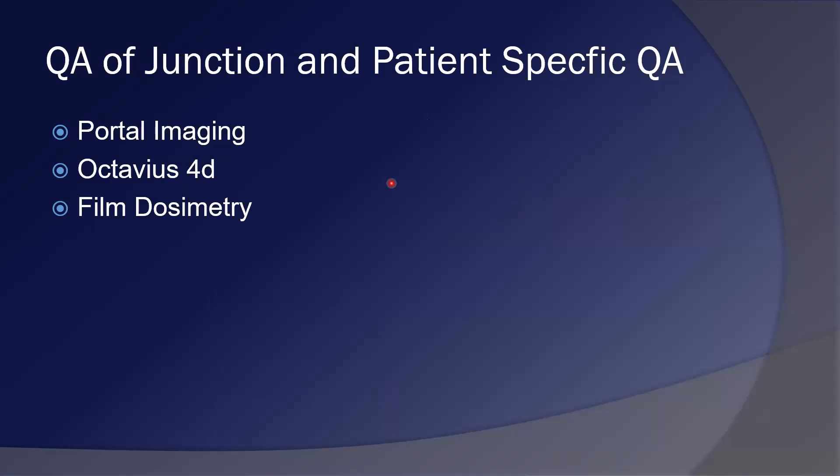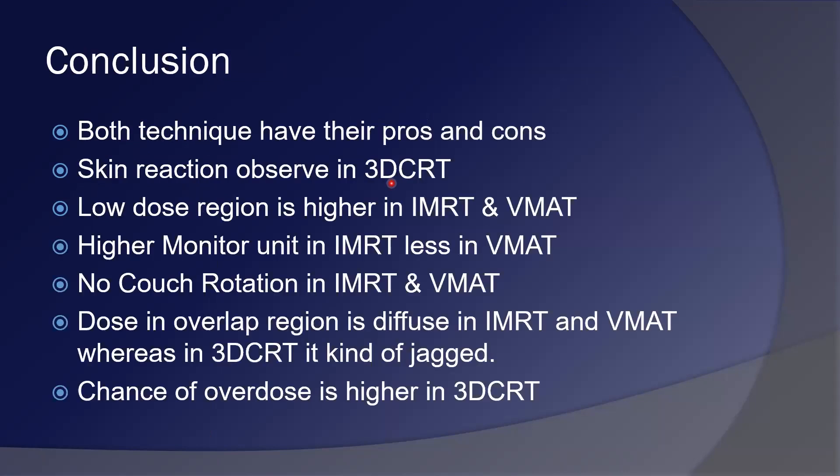For QA of the junction: in 3D CRT, junction QA is important and can be done with film dosimetry. For IMRT and VMAT, patient-specific QA is important and can be done with portal imaging. The Octavius 4D system allows coverage of large fields, and film dosimetry can be used with large film formats.